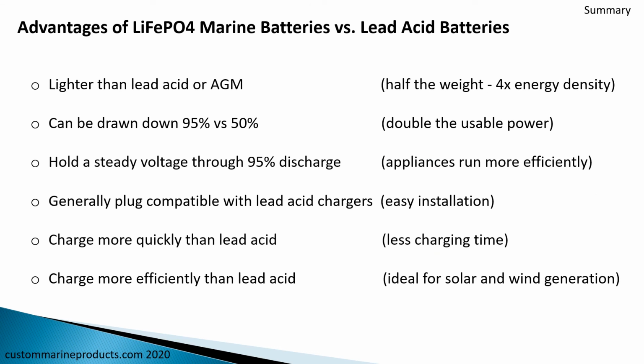So let's just take a look at the advantages of lithium iron phosphate over lead acid as kind of a recap here. First of all, they're lighter than lead acid, literally half the weight or 4 times the energy density. Because they can be drawn down 95%, you have almost double the usable power in the same size battery of lithium iron phosphate versus lead acid. You can hold a steady voltage through that 95% discharge. So your appliances are going to run more efficiently, which means they're going to pull less power. Generally, these are plug compatible with your lead acid chargers. So installation is easy. We do, as we just talked about, recommend some reprogramming of the chargers if possible.